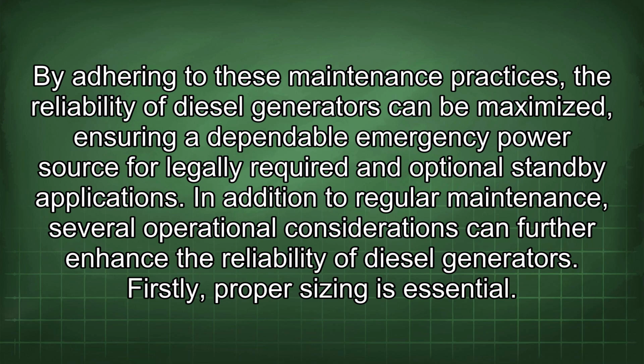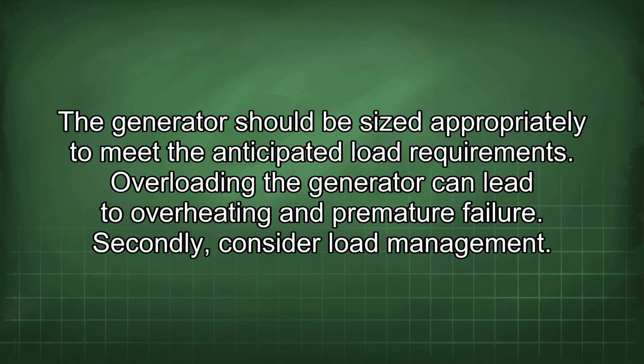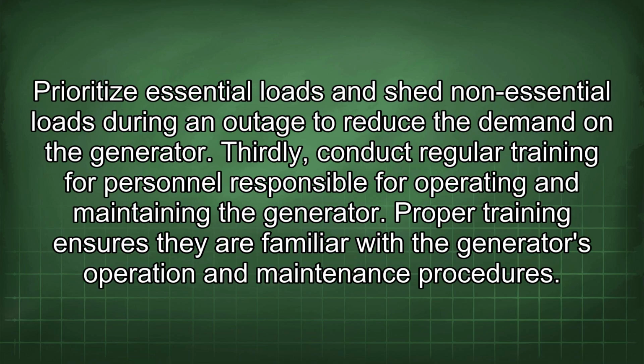In addition to regular maintenance, several operational considerations can further enhance the reliability of diesel generators. Firstly, proper sizing is essential. The generator should be sized appropriately to meet the anticipated load requirements. Overloading the generator can lead to overheating and premature failure. Secondly, consider load management. Prioritize essential loads and shed non-essential loads during an outage to reduce the demand on the generator. Thirdly, conduct regular training for personnel responsible for operating and maintaining the generator. Proper training ensures they are familiar with the generator's operation and maintenance procedures.